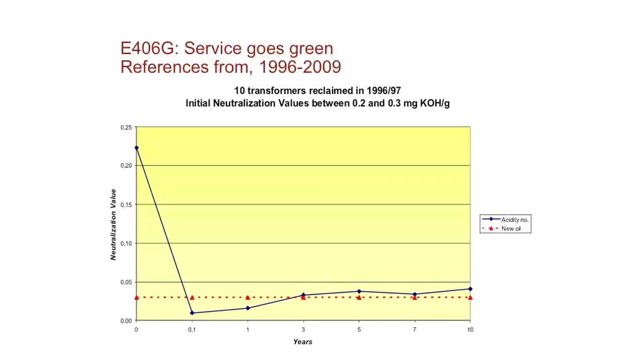I've got a couple of slides that show the increased level of acidity or neutralization to identify that we can bring the acidity number down to near 0.01, and then it stabilizes over time. Again, this is an average of 10 transformers. The red line here in each of the slides represents factory grade or refinery grade oil.